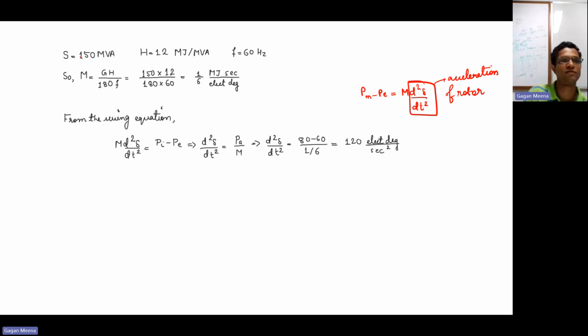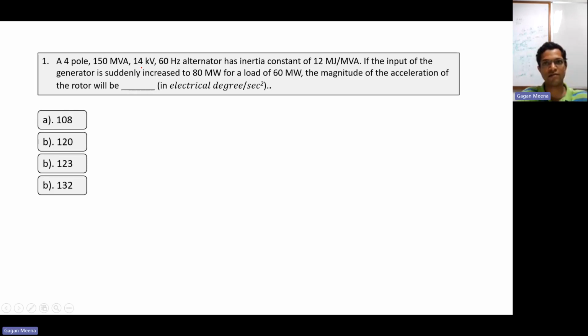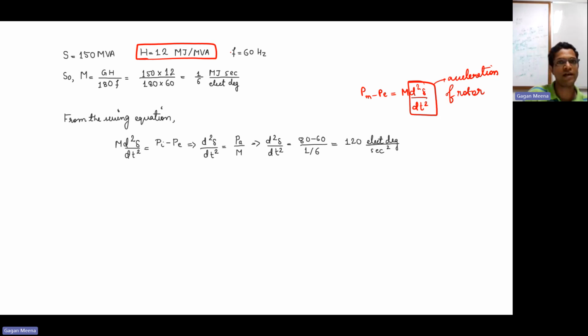First we need to find M. We have S equals 150 MVA and H is given as 12 megajoule per MVA. We need to find M. Frequency is 60 hertz. M equals H only, S into H divided by 180 into F.